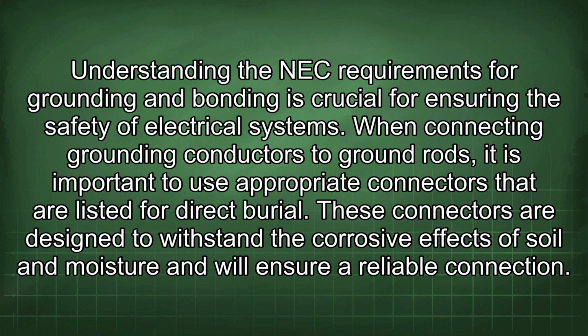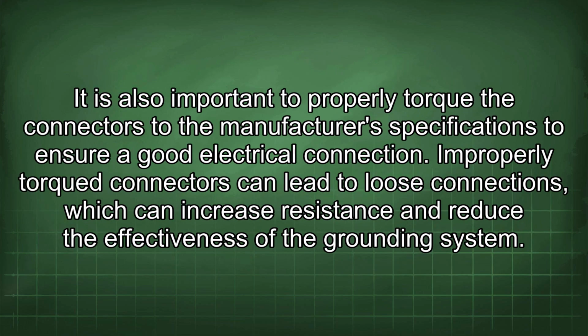When connecting grounding conductors to ground rods, it is important to use appropriate connectors that are listed for direct burial. These connectors are designed to withstand the corrosive effects of soil and moisture and will ensure a reliable connection. It is also important to properly torque the connectors to the manufacturer's specifications to ensure a good electrical connection. Improperly torqued connectors can lead to loose connections, which can increase resistance and reduce the effectiveness of the grounding system.